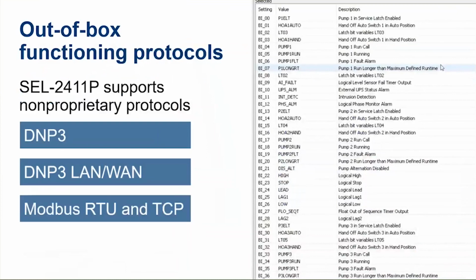We talked a little bit about the protocols that are available within the product. We want to make this as simple as possible for you to work with your existing SCADA system, your existing annunciation system. So we have multiple protocols in the product that are public: DNP3 and Modbus over Ethernet or serial. Modbus supports up to 2 masters, DNP3 supports up to 5, and you can do multi-protocol over Ethernet connections. It really provides a flexible solution for customers that are migrating from maybe a Modbus master to a DNP3 type of system, whether it's from serial to Ethernet. It's very flexible and can really help as you upgrade your system and add new protocols.